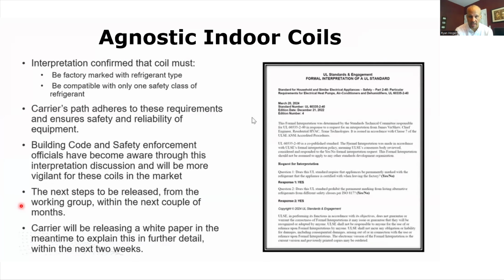Assuming you guys have seen those. The original ADP Flex coils, and we don't sell ADP or anything, I'm just educating people. The ADP Flex coils that came out last year were ones where you had one coil part number, and you could use it for R-22, 410A, 454B, or R-32, any one of those four refrigerants. You basically bought the coil, you told them what refrigerant you were going to use at the counter, and they handed you the expansion device for that refrigerant, and you put that on yourself.